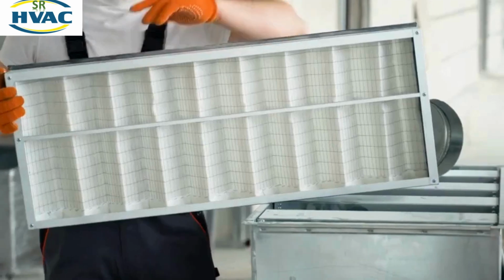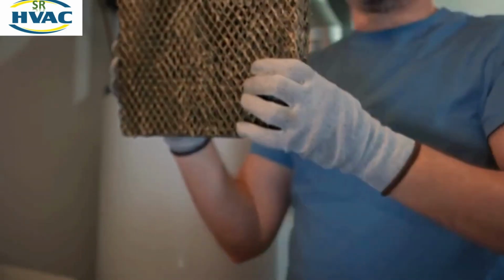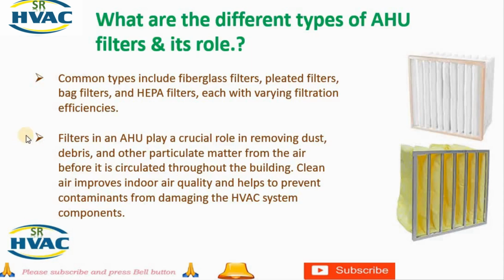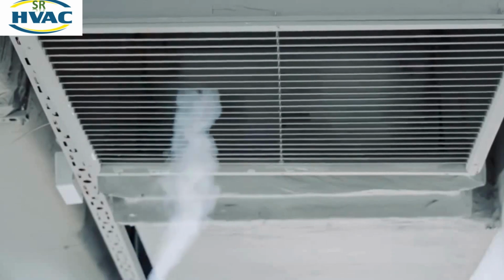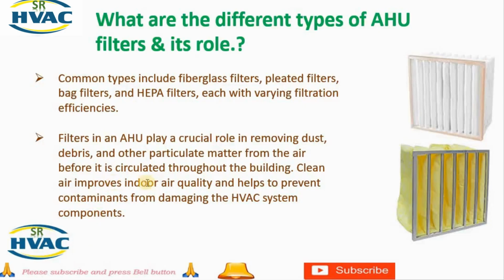Common types include fiberglass filters, pleated filters, bag filters, and HEPA filters, each with varying filtration efficiencies. Filters in an AHU play a crucial role in removing dust, debris, and other particulate matter from the air before it is circulated throughout the building. Clean air improves indoor air quality and helps to prevent contaminants from damaging the HVAC system components.